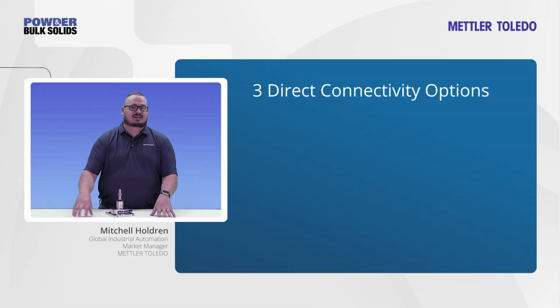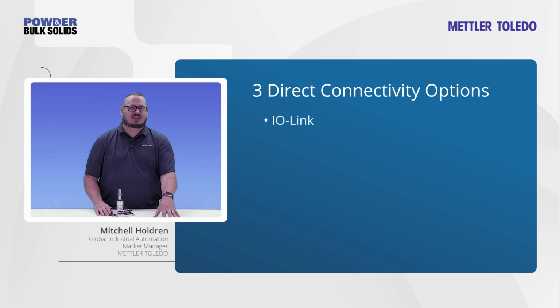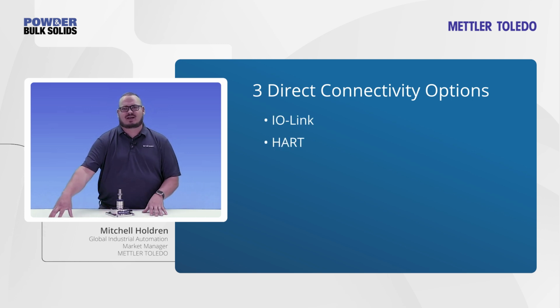You won't put something bad into your process or application without immediate notification and the ability to easily correct it. Mitchell, what automation connectivity options are available, and what kind of data can users receive? Sure. So with the AnyLevel, what we have are 3 distinct connectivity options. We have IO Link, we have HART, and we also have 4 to 20 milliamp, or analog output.